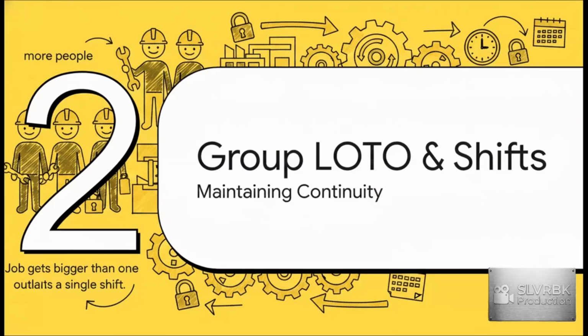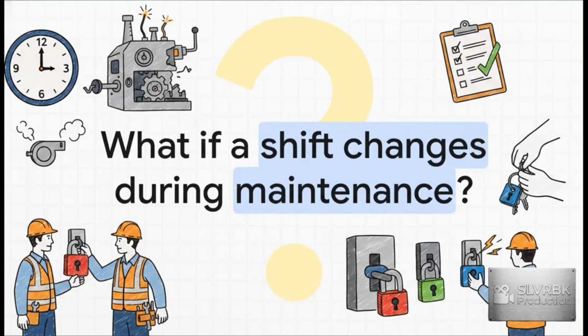Section 2. Group LOTO and shift changes, maintaining continuity. So what happens when a job gets bigger than one person? When that 5 p.m. whistle blows and the machine is still in pieces, you can't just toss the keys to the next guy or leave the equipment unlocked. There has to be an orderly, documented handoff between the outgoing and incoming shifts. The incoming crew actually has to verify the energy isolation for themselves. You really can't just take the last shift's word for it.